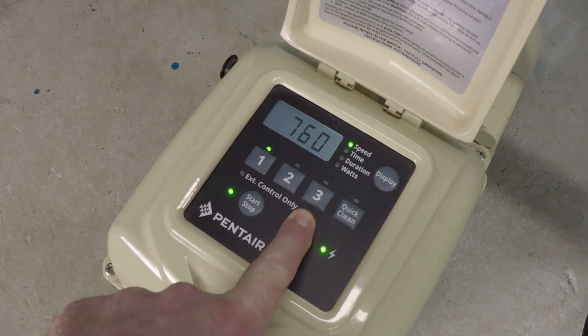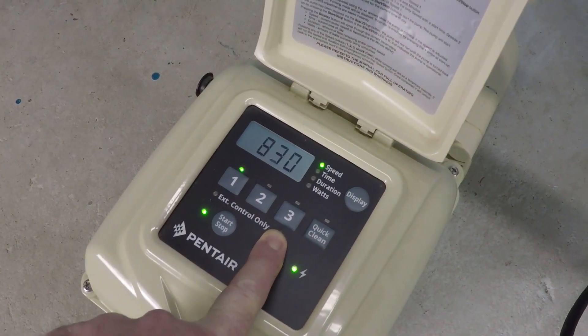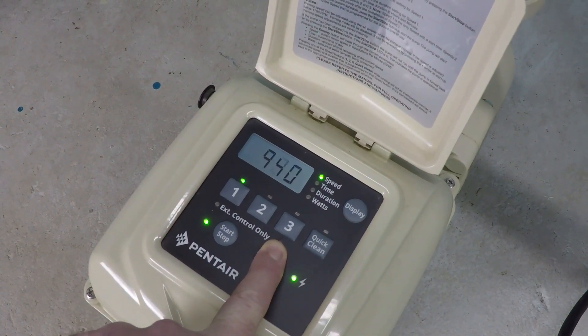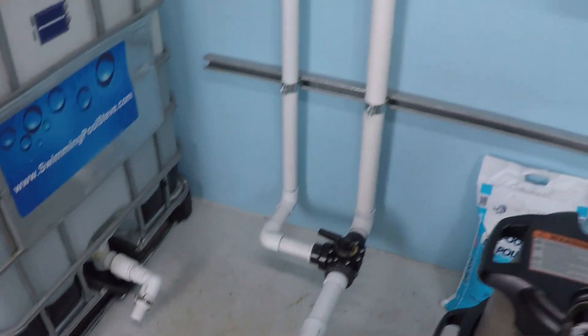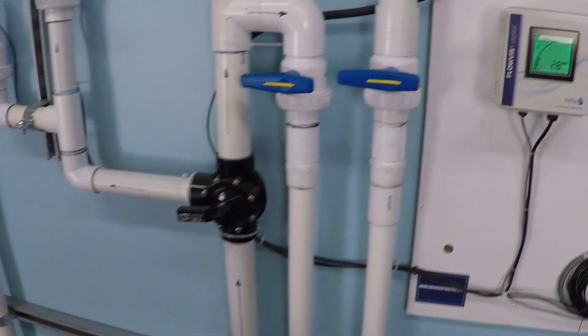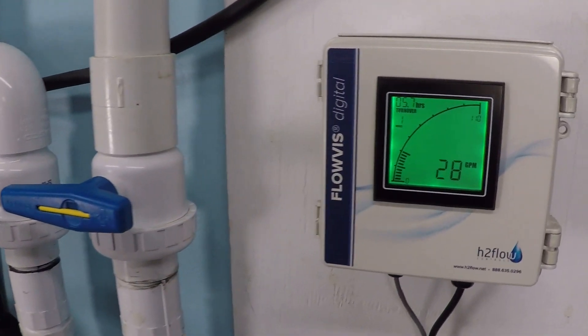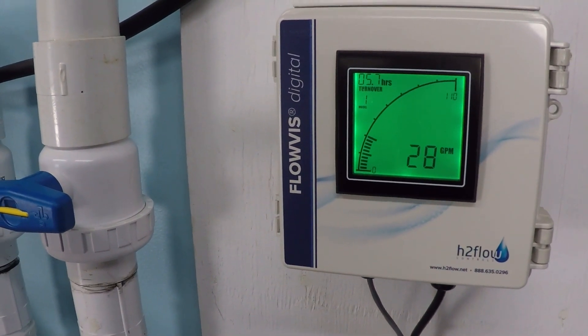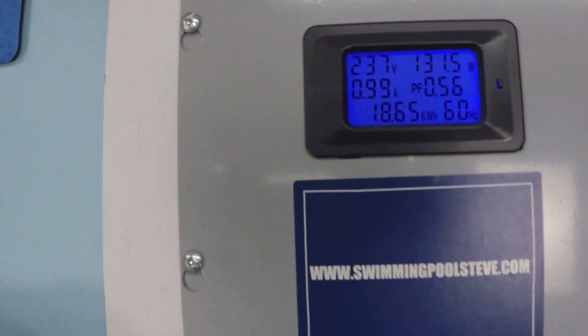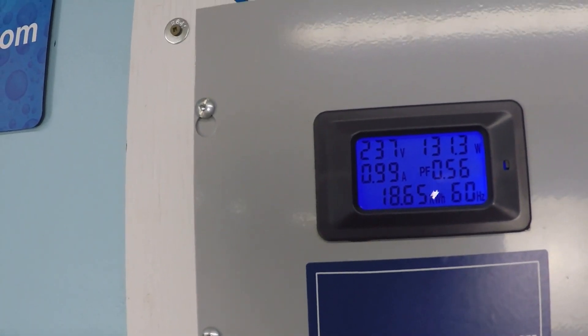So let's go ahead and jump up to a thousand here. Really quiet. Variable speed pumps are extremely quiet especially at the low RPMs. We're up to about 28 gallons per minute and just over 131 watts of power consumption.